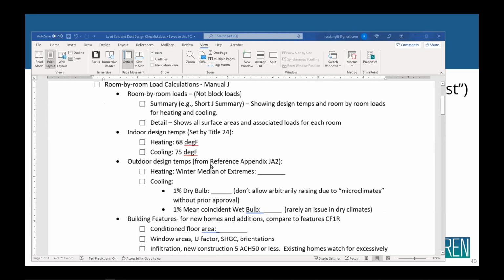Okay, outdoor design temperatures, reference Manual J, and write down what it is for your jurisdiction. If you're in a county, you might have several different design temperatures. If you're in a city, there's really only one you have to worry about. Write those down and make sure that people do load calcs and use those temperatures. Don't allow them to arbitrarily, you know, bump it up just to quote unquote be safe. You know, there's a reason, and there's a long and practiced and tested methodology for using design temperatures, and there's no reason to mess around with them.